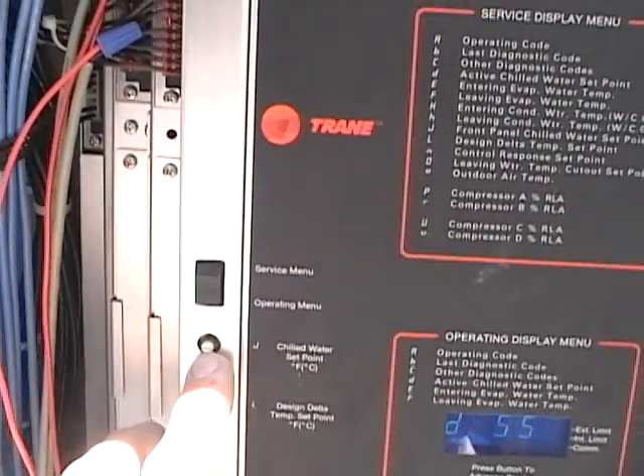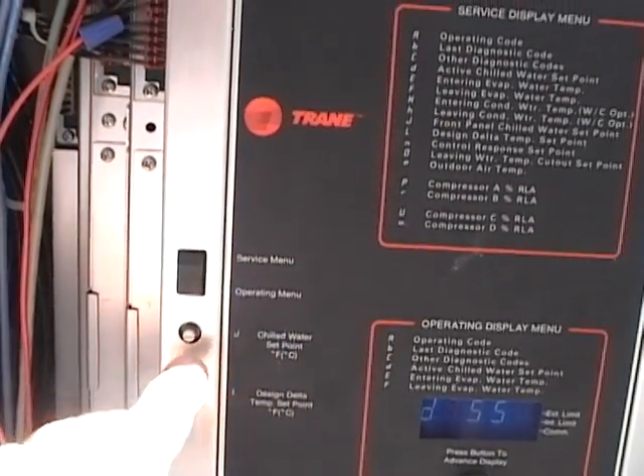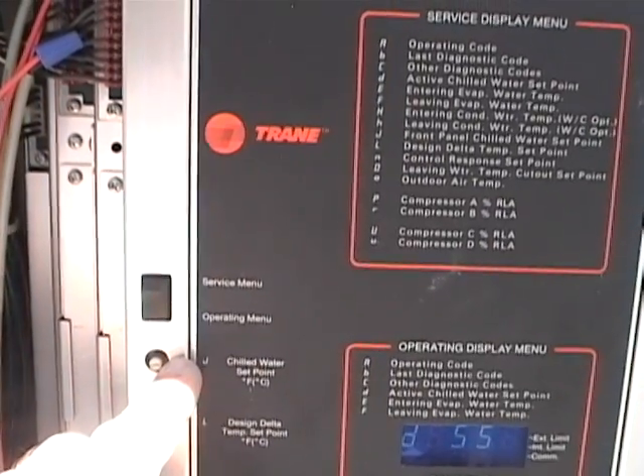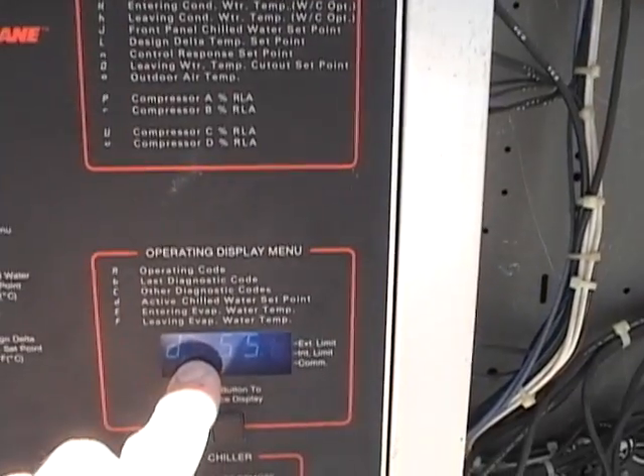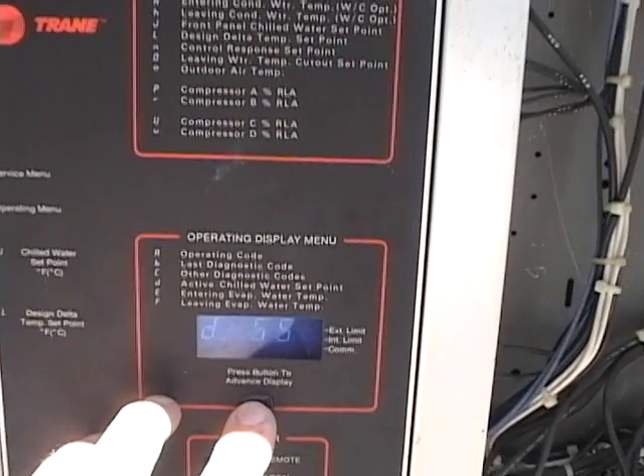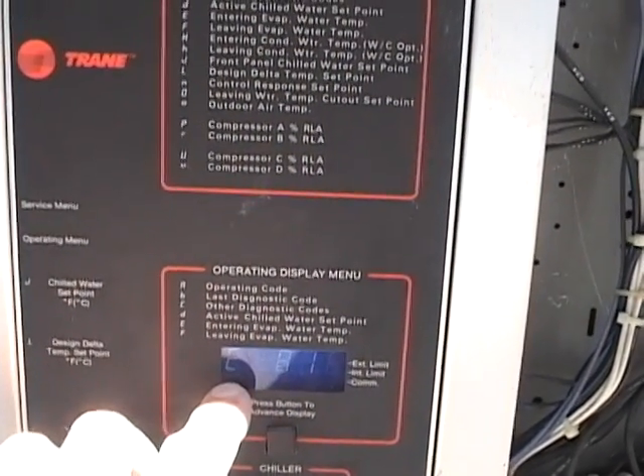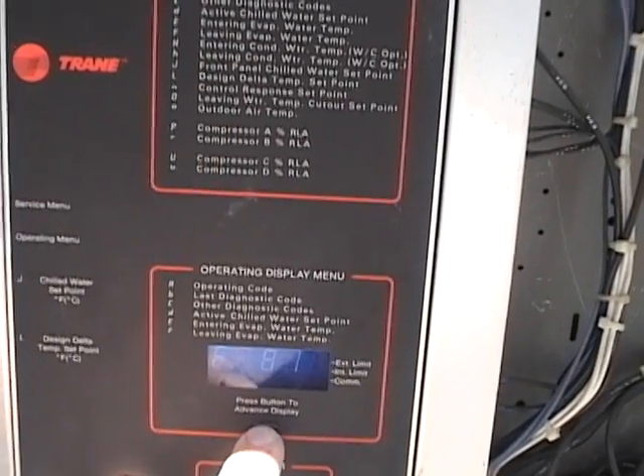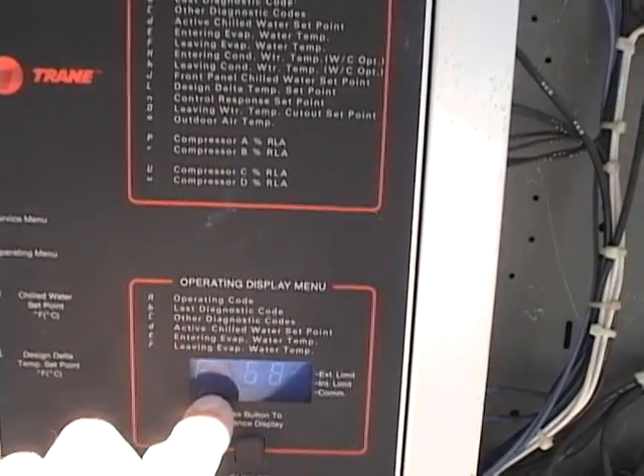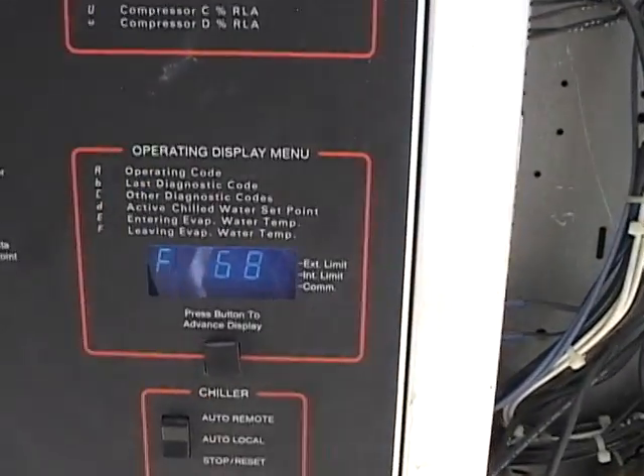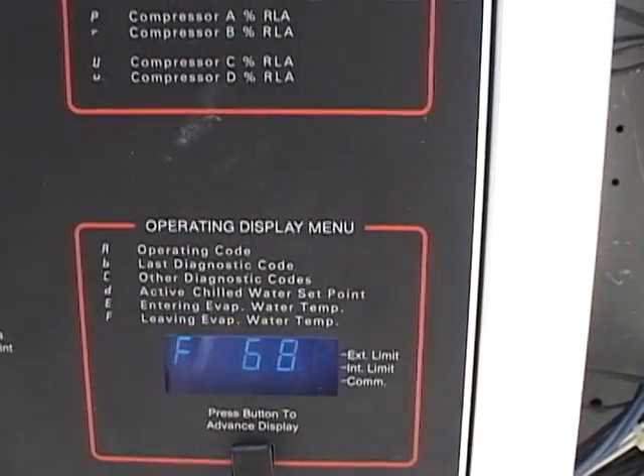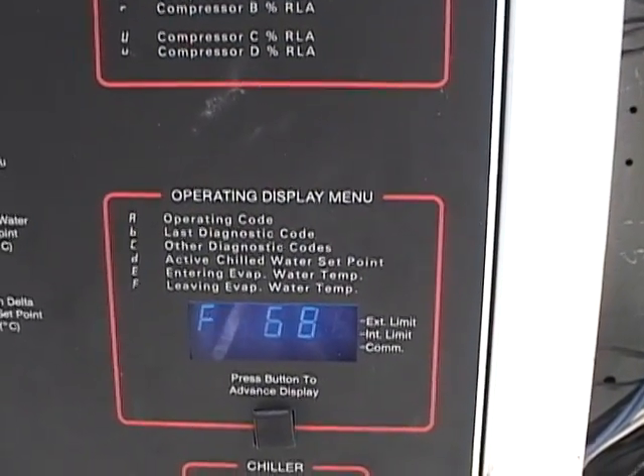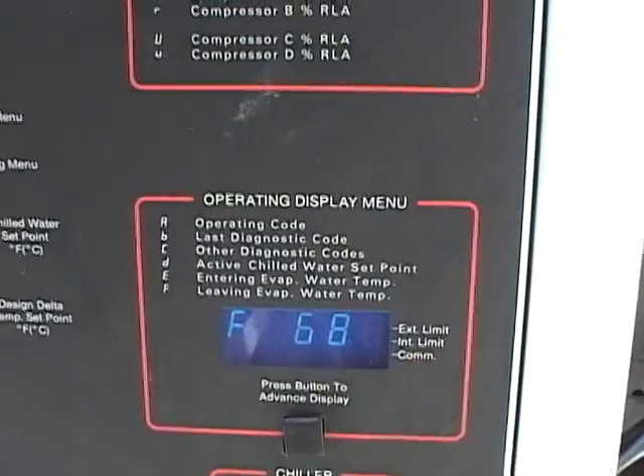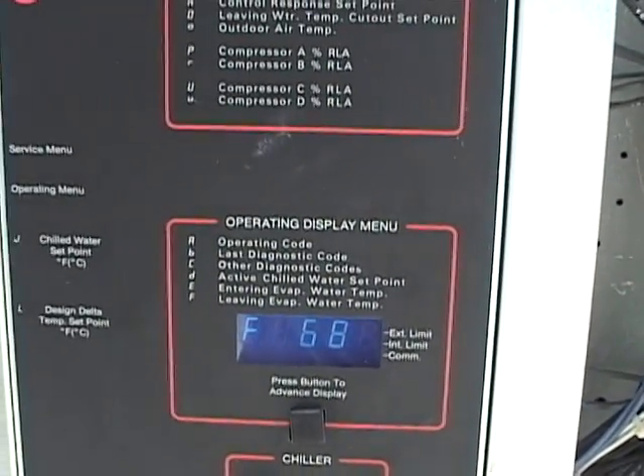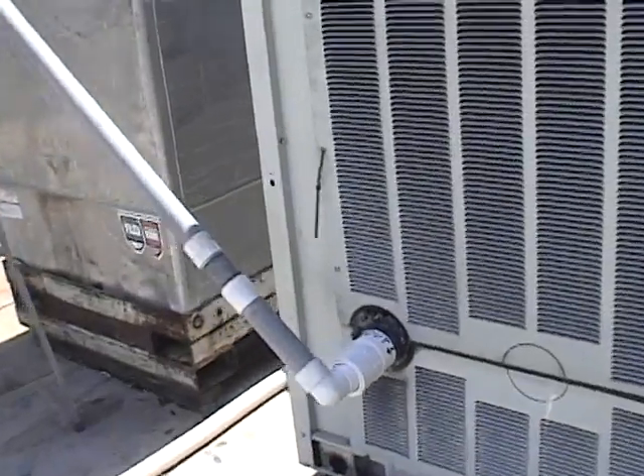You set our set point right here. We have the chilled water set point. Very simply turning this will bring it up or down, your set point for your temperature. Currently I have it set at 55 degrees Fahrenheit. The water entering the chiller is 81. The temperature leaving the chiller is 69. Now it's 68. You'll notice it keeps dropping the temperature. What I have is the water looping through the heat exchanger on the unit up into a holding tank, coming out of here and going up over into a large holding tank over here.